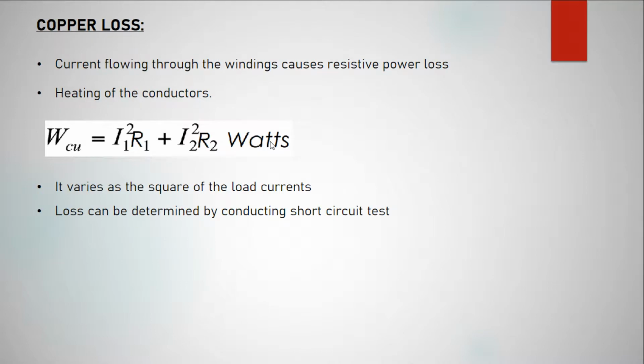Next comes copper loss. Current flowing through the winding causes a resistive power loss. When the primary is supplied with voltage, primary current flows through the primary winding of the transformer. When a load is connected to the secondary, secondary current flows through the secondary coil. When current flows in both coils, there is definitely a power loss, given by I1^2 R1 and I2^2 R2. Together they create copper loss, because current flows in the copper windings of the transformer. It varies as the square of the load current, which is very important, because in the formula it is I1^2 and I2^2. This loss can be determined by conducting a short circuit test.